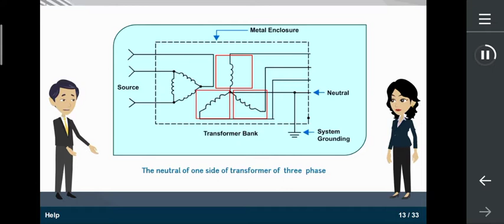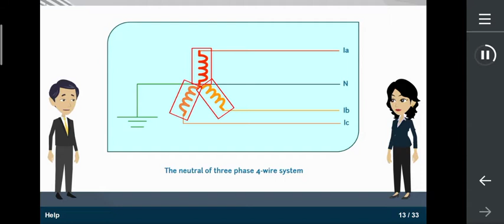To answer your question, what is to be earthed? There are quite a few points to consider. Firstly, the neutrals of all power systems should be earthed, such as the neutral of one side of transformer of three-phase bank. As you can see in this image here, there are three phases and the neutral point is grounded. The neutral of three-phase four-wire system. This image shows three phases denoted by IA, IB and IC and neutral N. As you can see, the neutral is grounded denoted by the green line.